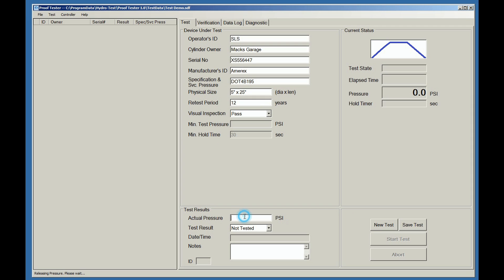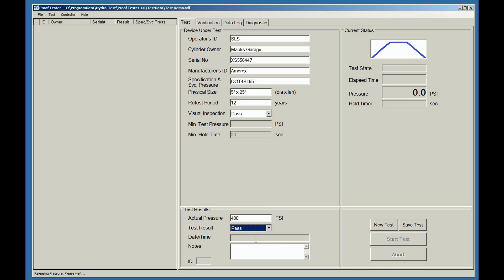We then click down on the Actual Pressure tab and this is where we type in the actual pressure that we went to. In this scenario, we should have gone to a minimum of 390 PSI. We actually went to 400. We held the pressure and it passed. And we can put a note in here.